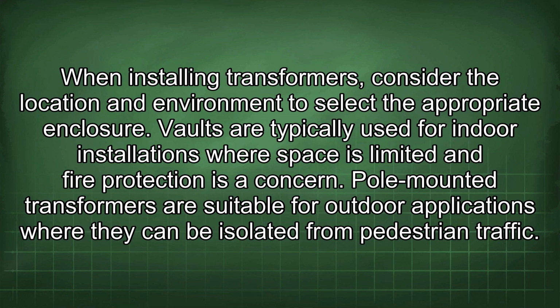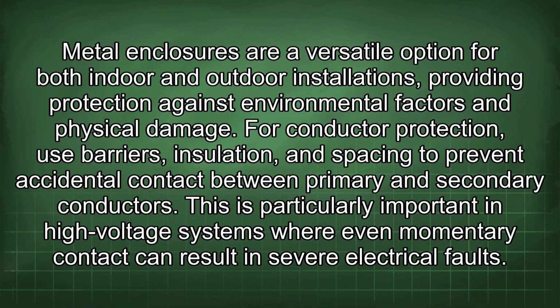When installing transformers, consider the location and environment to select the appropriate enclosure. Vaults are typically used for indoor installations where space is limited and fire protection is a concern. Pole-mounted transformers are suitable for outdoor applications where they can be isolated from pedestrian traffic. Metal enclosures are a versatile option for both indoor and outdoor installations, providing protection against environmental factors and physical damage.